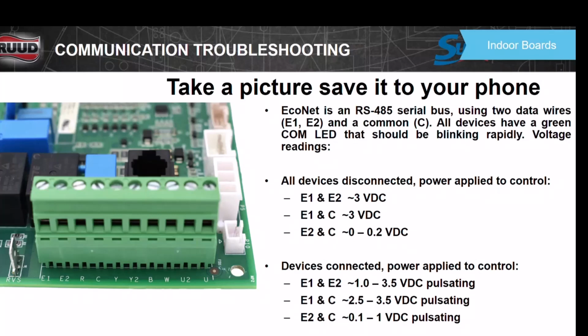I would take my wires off of the outdoor unit and go to the next component and check it, then pull them off that and then go to the next one. That way you eliminate it if you had a short in the outdoor unit that was causing communication problems, taking the whole communication circuit down. At least you just eliminated that one, right? Basically, check it with it connected and without it connected, and that's going to tell you where your problem is.